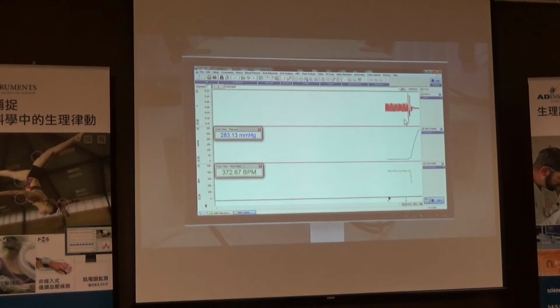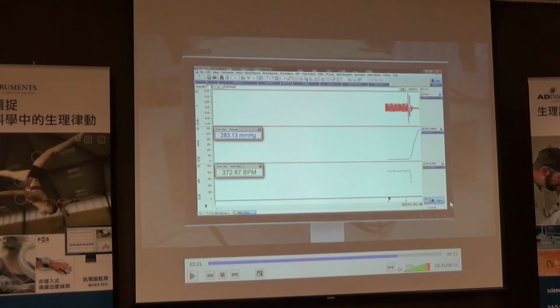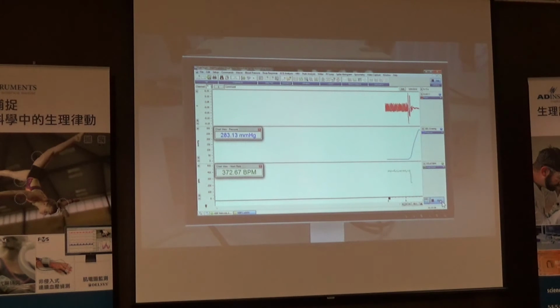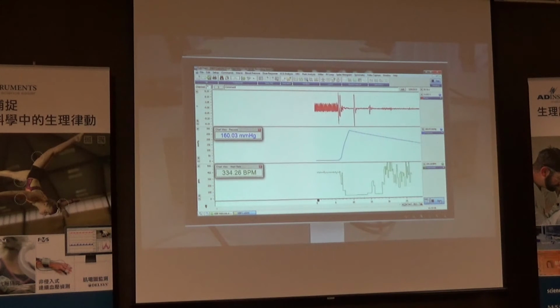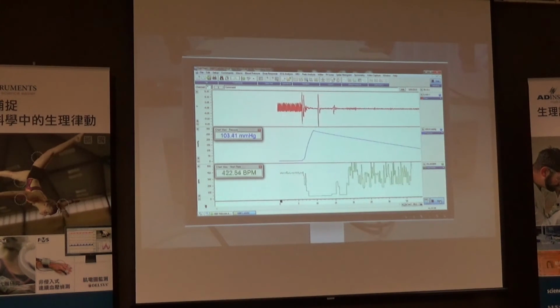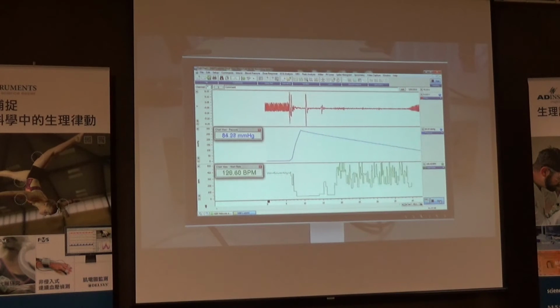You press the button, the pressure will go up. At some point, it will block the pulse. Then it will automatically start deflating, and when the first pulse comes, that gives the systolic pressure. The pulse signal should start to decrease as the cuff starts to occlude the blood flow, up to the preset maximum cuff pressure. When the maximum cuff pressure is reached, the pump will stop and the pressure will begin to drop slowly. As the pressure drops, the pulse signal will start to increase again.